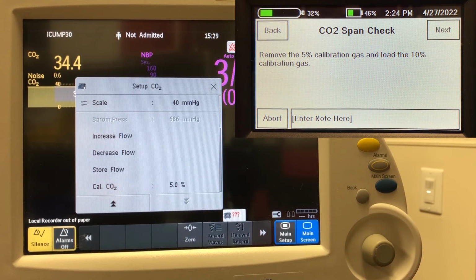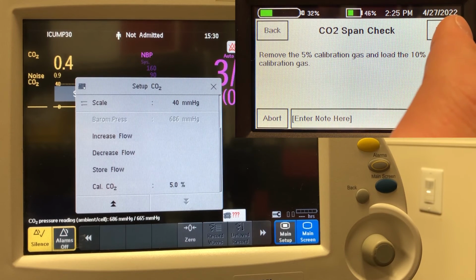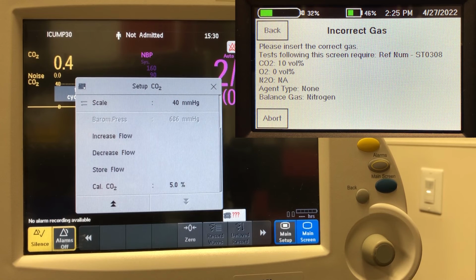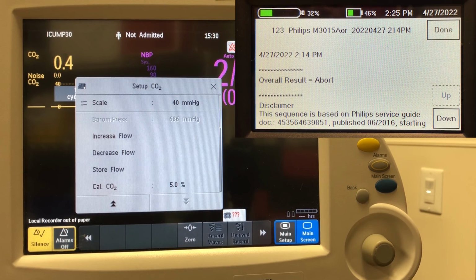Now we're going to do a CO2 span check. So to do this, we've got to take the CO2 bottle that's in the Smart Tank out and replace it with the 10% bottle. I don't have that 10% bottle with me, so I'm not going to be able to complete this, but this is the last step in the sequence. You have that in there, you hit next. You can see in this case it's telling us incorrect gas because I still have the 5% gas bottle in there. So I'll abort the test and be done. Here's the test report. You can see it shows that it's aborted.